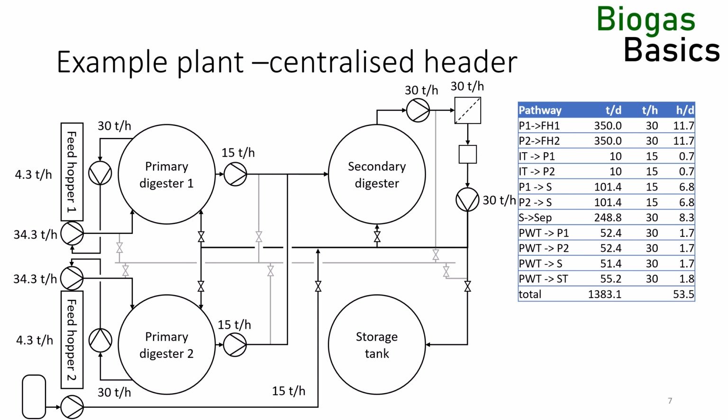I recently came across this system and thought it was an elegant configuration. It retains the advantages of a decentralized pumping system and gives the ability to pump from every tank to every tank. Simply connect the discharge side of all pumps to one central header pipe. This is not an expensive modification. The valves can even be manually operated valves. In normal operation, this pipe is not used, but it gives additional flexibility.